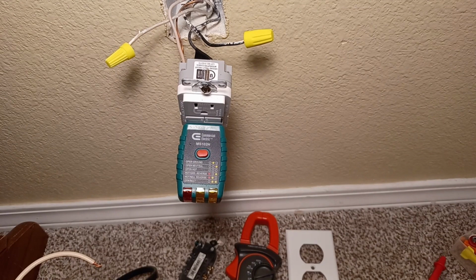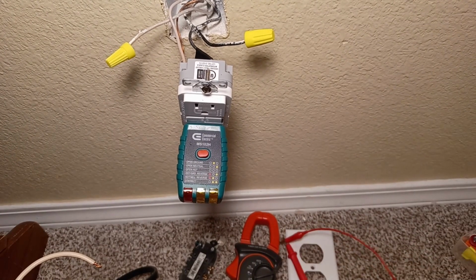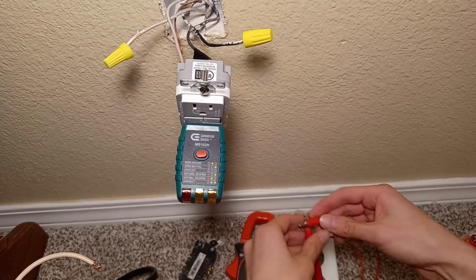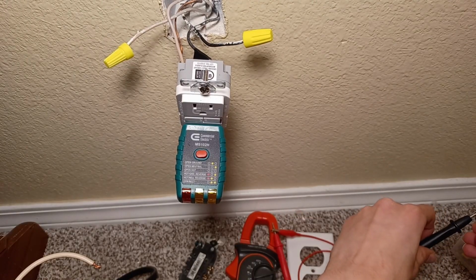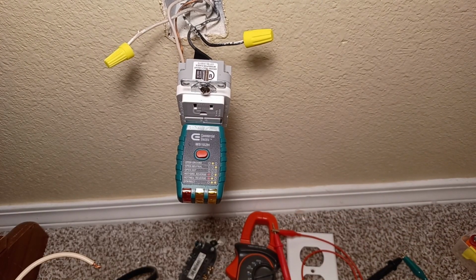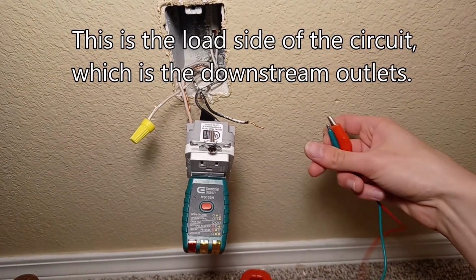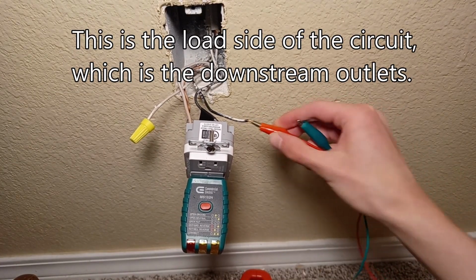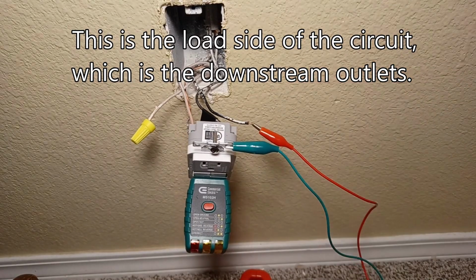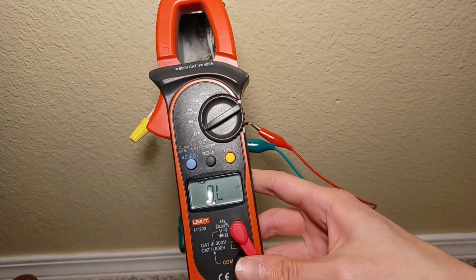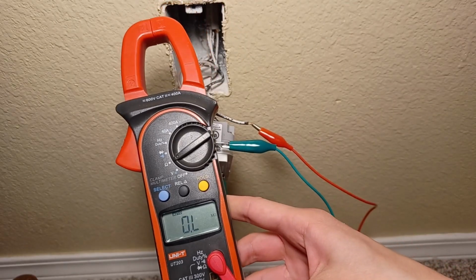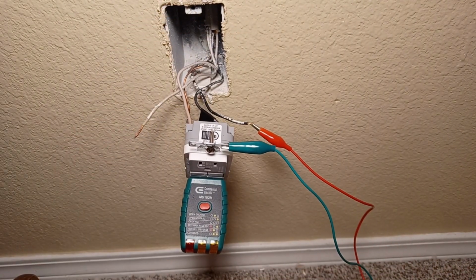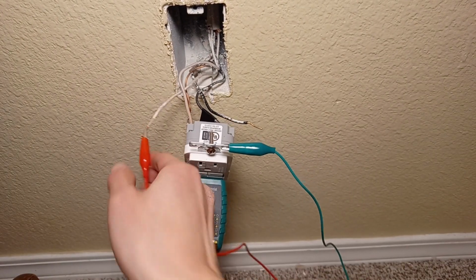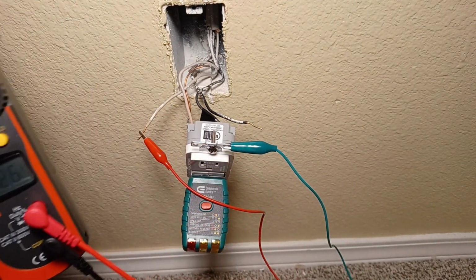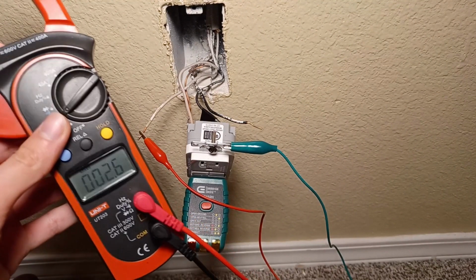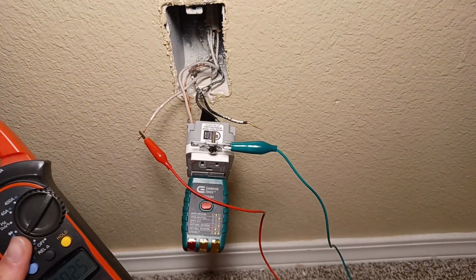Have my multimeter on the ohms range. I'll connect one probe of it using an alligator clip to ground. And I'll connect the other probe of it using another alligator clip to the hot side. If I disconnect the hot wire and put one clip on here, then connect to the grounded metal strap of the GFCI, we have an open circuit. So it's not directly shorted. What about neutral? Ground. Oh, 2.6. What? Now that's why it instant trips. Neutral and ground aren't supposed to be shorted.